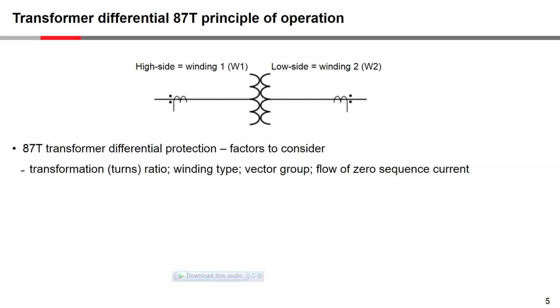Now when we're looking at protecting transformers with 87T, or transformer differential protection, there are a number of factors to consider. Generally these are the transformer turns ratio, because the voltage on the winding 1 and winding 2 side is different, and so for balanced current flow, the current flowing into one winding and flowing out from the other winding is not the same magnitude. We need to look at the winding type, whether it's a delta connected winding or whether it's a Y connected winding.